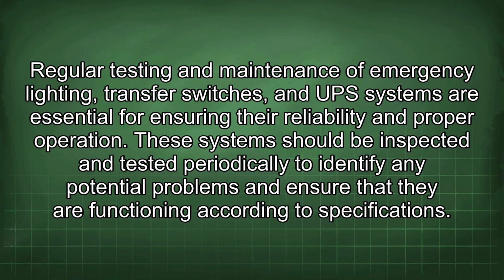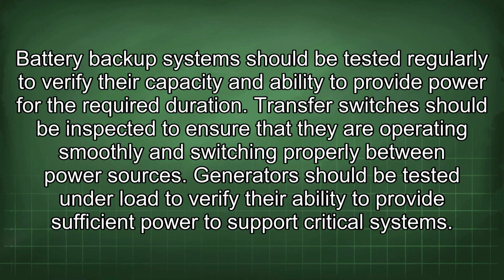Regular testing and maintenance of emergency lighting, transfer switches, and UPS systems are essential for ensuring their reliability and proper operation. These systems should be inspected and tested periodically to identify any potential problems and ensure that they are functioning according to specifications. Battery backup systems should be tested regularly to verify their capacity and ability to provide power for the required duration. Transfer switches should be inspected to ensure that they are operating smoothly and switching properly between power sources. Generators should be tested under load to verify their ability to provide sufficient power to support critical systems.